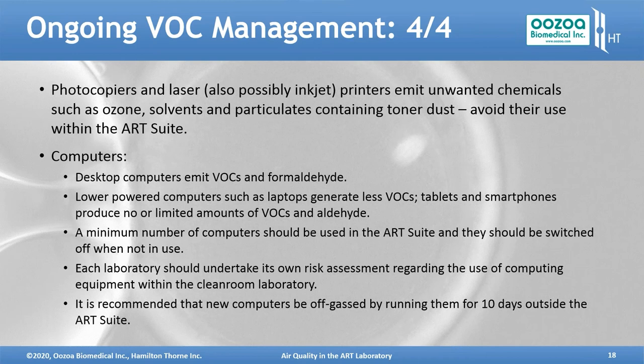It's not an absolute, but you need to understand that these are a source of VOCs and potential harmful things to the embryos. So you need to understand them and design your systems having understood that and manage the risk appropriately. So every laboratory should undertake its own risk assessment regarding the use of computing equipment within the clean room. If you're buying new computers, particularly towers, they need to be off-gassed by running for 10 days outside the ART suite. And you could always test what's happening with those for the off-gassing by using a VOC meter.